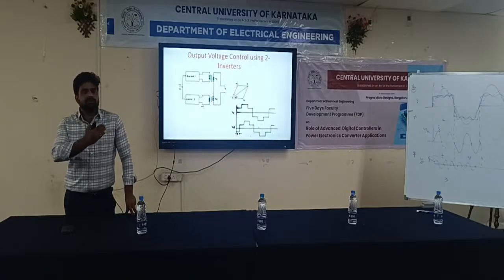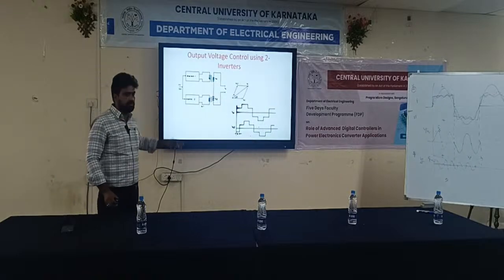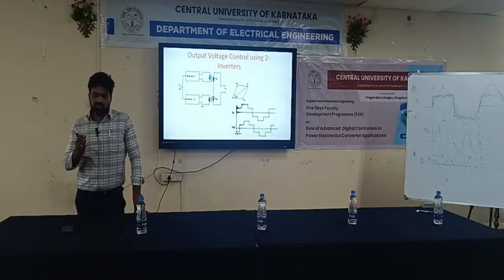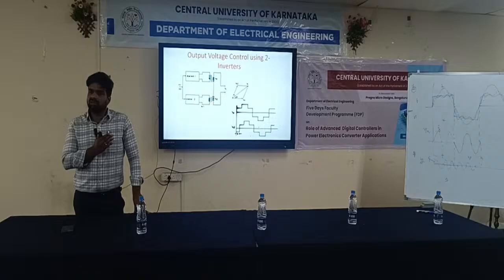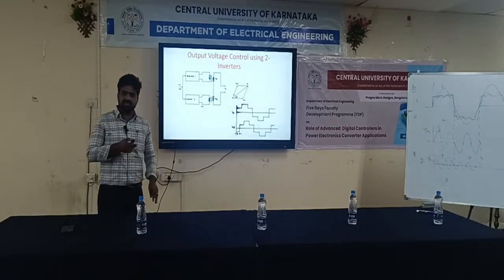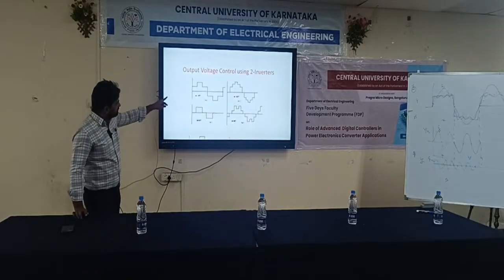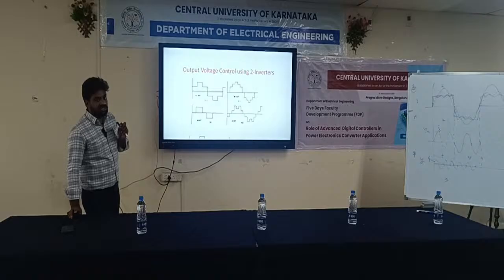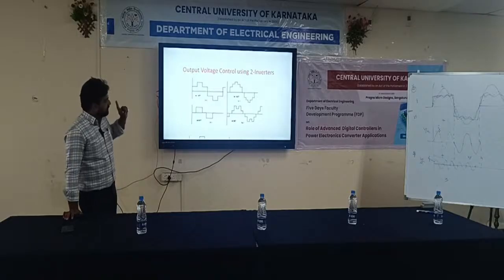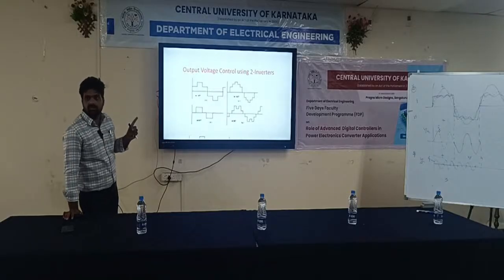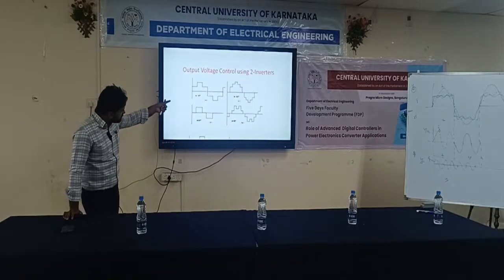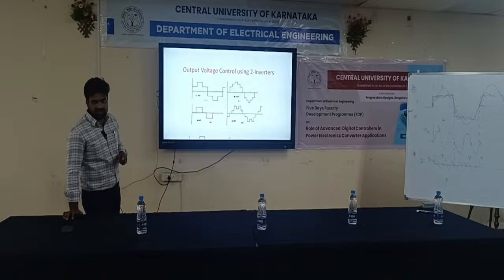of order less than the pulse number will automatically cancel. Like now you are going to go for a 12 pulse inverter, the harmonics which are lesser than 12 pulse will automatically nullify, and that's the reason the shape of your voltage remains much more sinusoidal. So if you want to achieve such a target, the phase difference in the transformer should be maintained at 360 divided by the pulse number, which gives the more sinusoidal voltage.